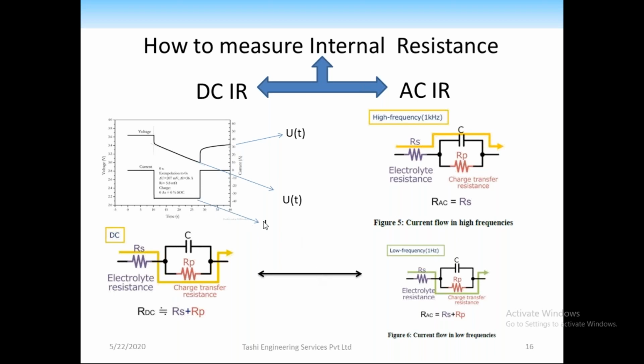The other option is to use an AC impedance meter. The impedance meter comes with two probes. You connect them to the two terminals of the cell, give a high frequency pulse, and get the value displayed on the screen. It hardly takes 15 to 20 seconds.